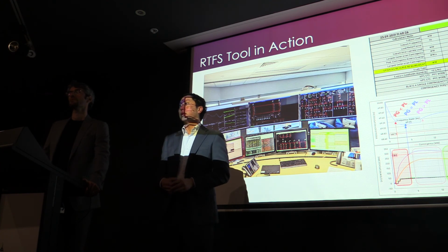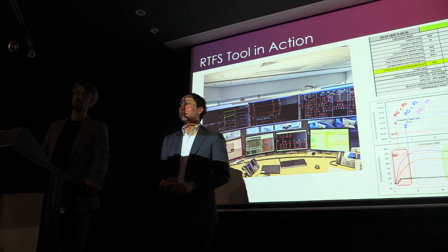I mean, with the AGCs, the units are setting their deadband and they're setting their min-max droop responses in those parameters. You know, I can recall that Blue Water had a problem that if it provided the technical rules' exact frequency droop response, it would swing. It would actually get larger swings under and over power because fuel's being fed in, it responds, it withdraws, and actually the modelling showed it could swing out of control, you know, trip off ultimately. So of course they just had to deaden their droop response to not let that happen.